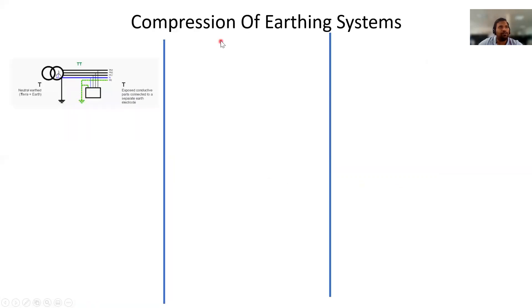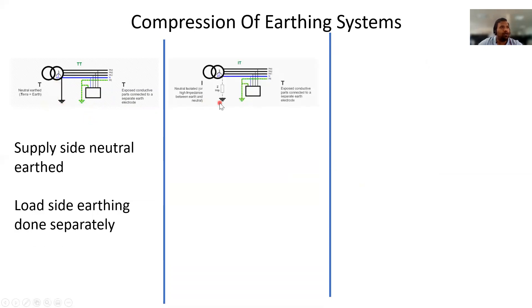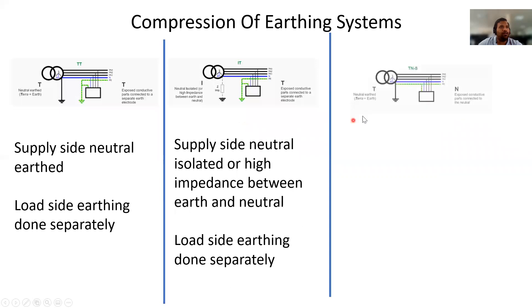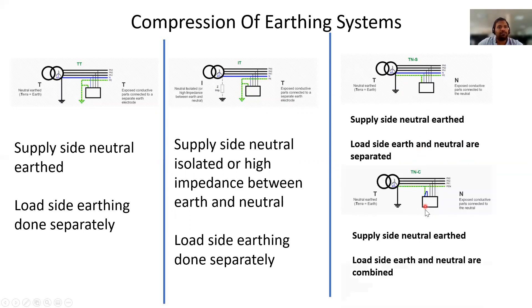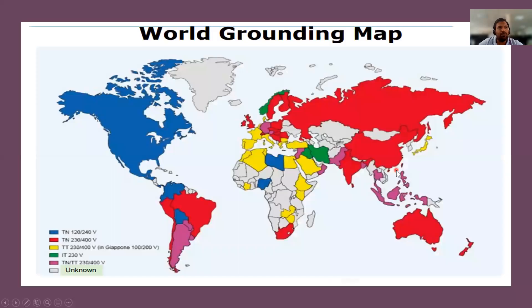A quick comparison between earthing systems: In the TT system, both the supply-side earth and load-side earth are separate. In the IT system, only the load side is earthed. In the TNS system, the supply side is earthed and a separate conductor runs to the load side with neutral and earth separated. In the TNC system, the supply side is earthed and the load-side neutral and earth are combined.